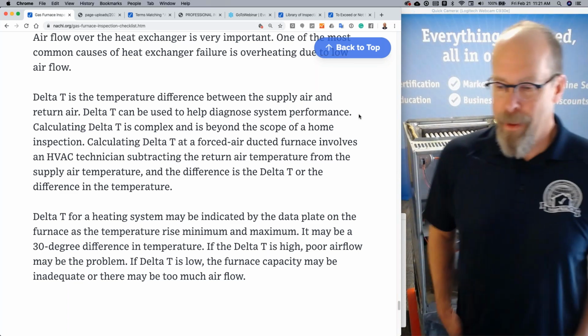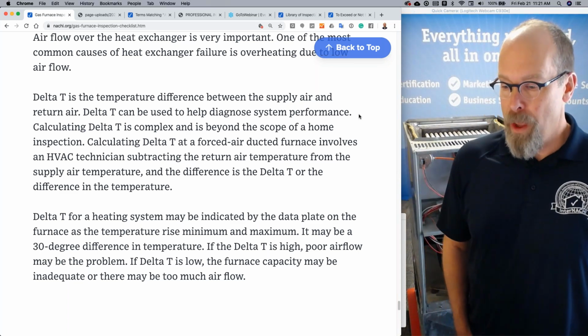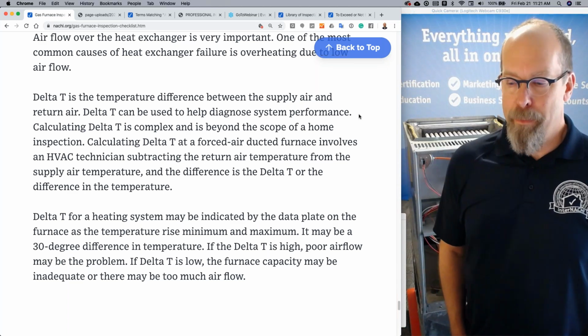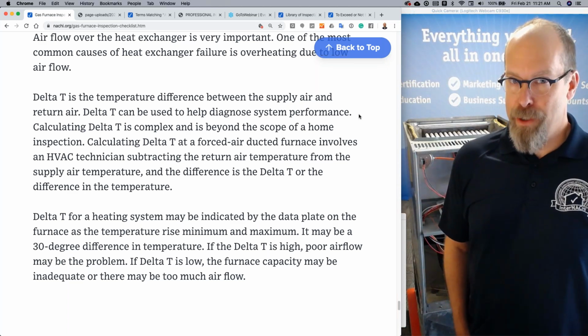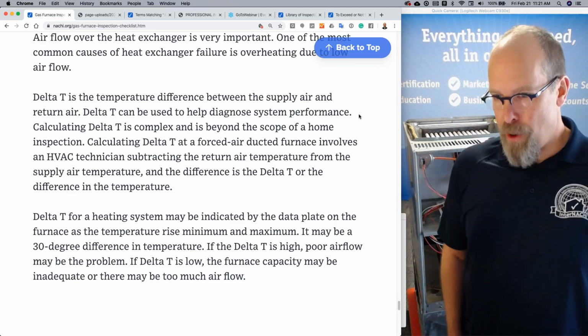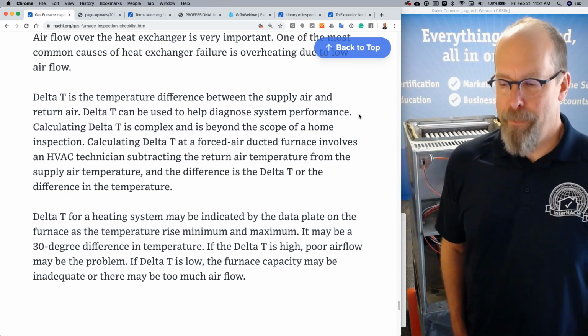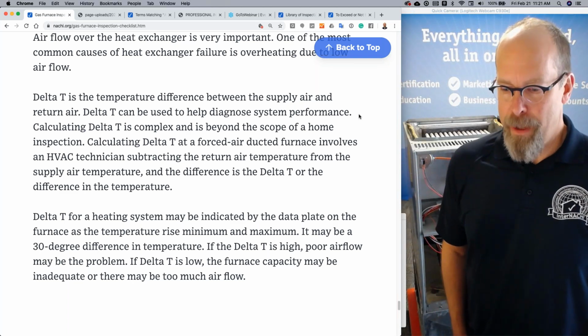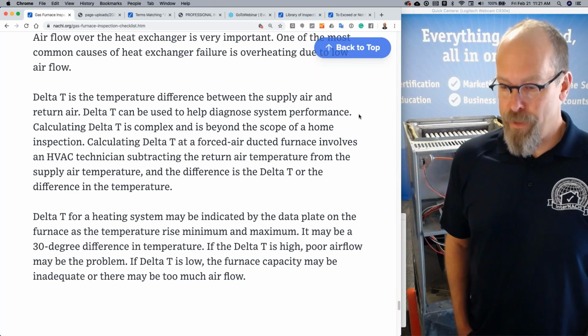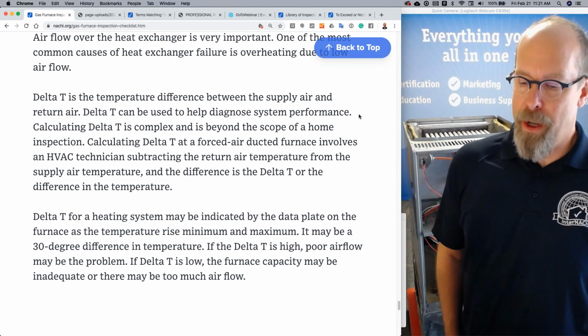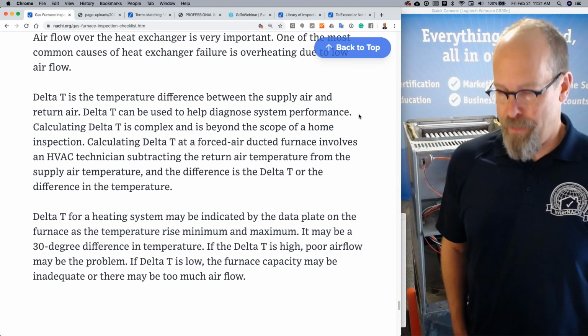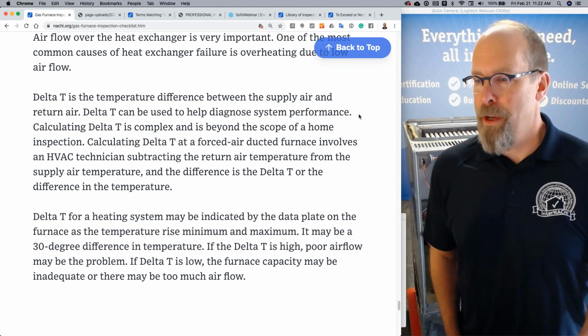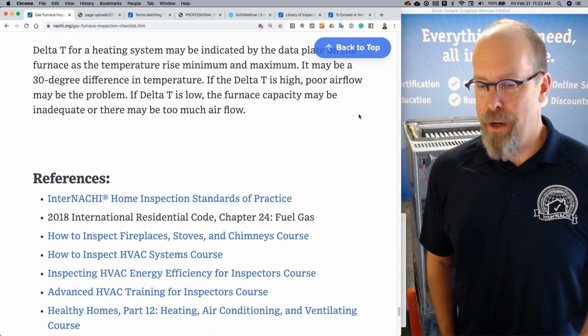Yep. If the delta T is too high, poor airflow may be the problem, right? If it's too hot, the airflow over the heat exchanger may be inadequate. If delta T is low, the furnace capacity may be inadequate, and there may be too much airflow. So, a little information about delta T and airflow.